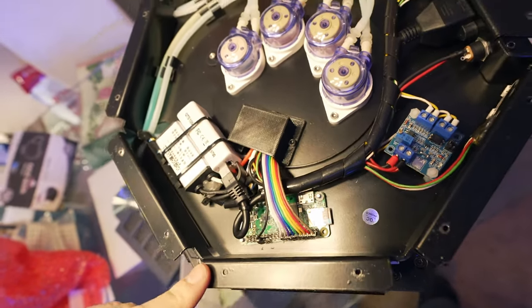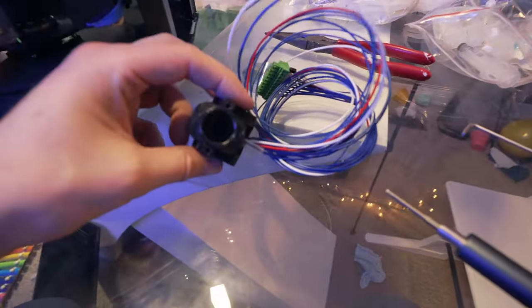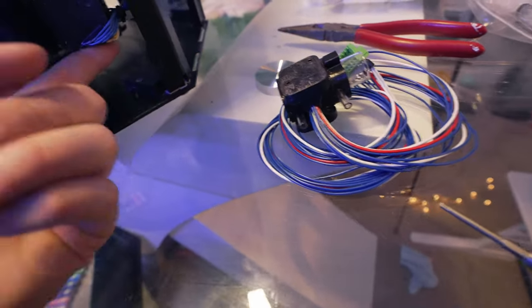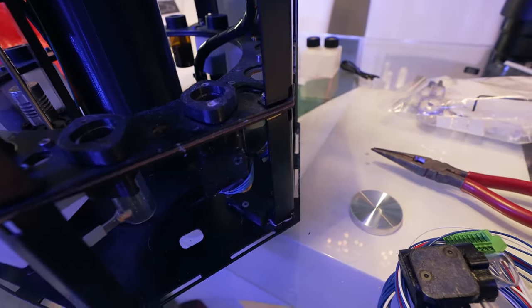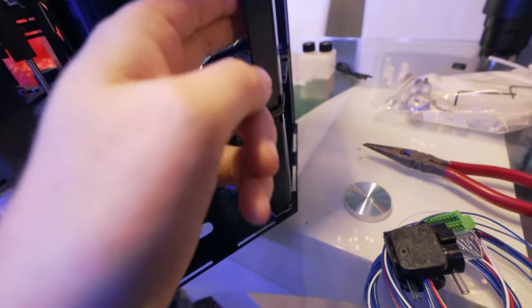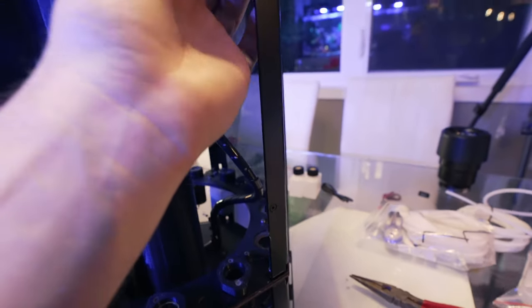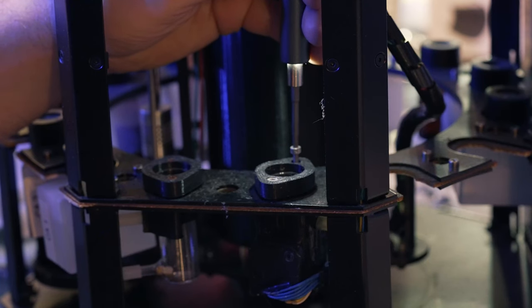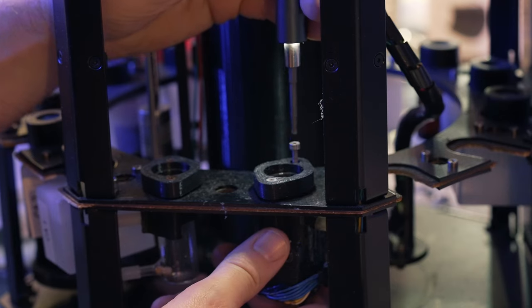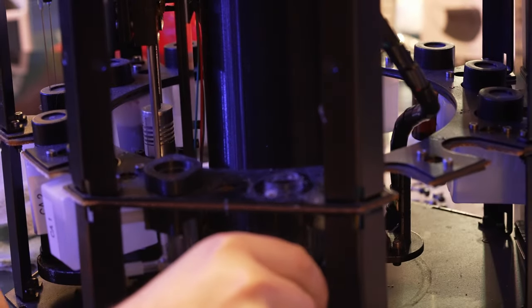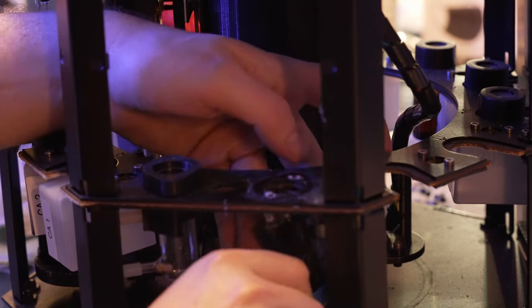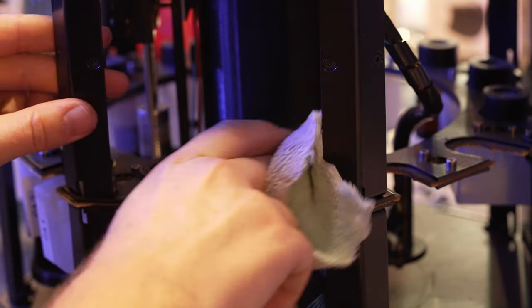Now, I think I'm going to tackle the hardest part first, which is going to be the reaction chamber. Everything else should be pretty easy after this. And to get this guy out, it looks like we just have the two screws on that collar on top, and we should be able to pop it out. Then the trickier bit will just be fishing all the tubes and the wires and getting that up top. I really appreciate that it's basically the same screws throughout the entire machine because it makes life much easier. So, it looks like we have a little ring on the top, and the reaction chamber just slides down from underneath. I'll give it a quick little wipe down.